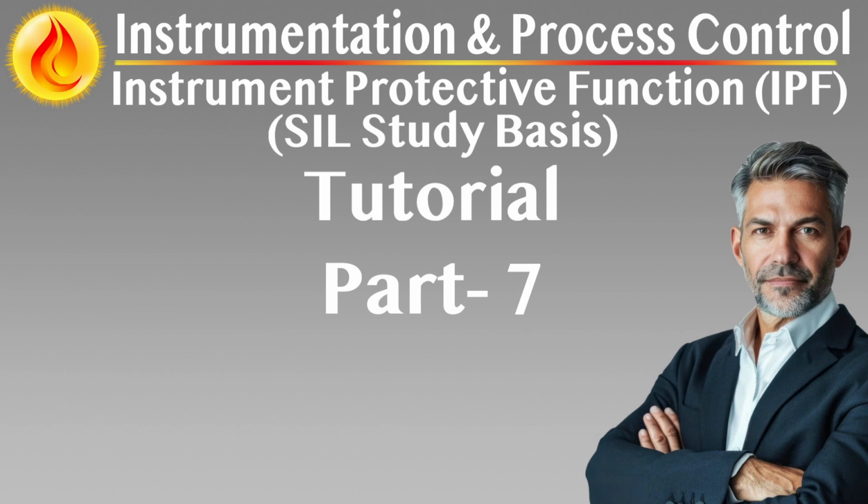Test planning and documentation. Test procedures must be standardized. Written instructions must define test scope, method, test equipment, acceptance criteria, and safety precautions. Test frequency determined by SIL requirements. Higher SIL functions require shorter test intervals to keep PFDavg within target limits. Frequencies must be documented in the Safety Requirement Specification, SRS, and maintained through a test schedule.